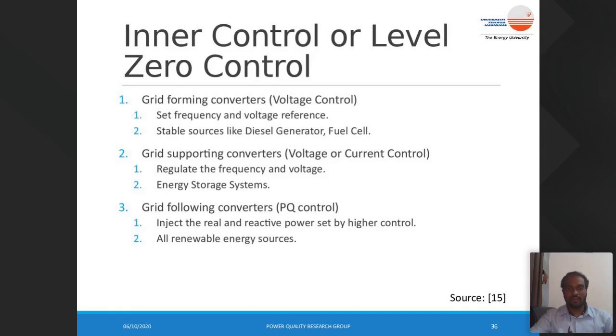And in case of an isolated microgrid, there would be at least one grid forming converter to set the frequency and voltage reference. And these converters are usually fed by stable sources like diesel generators or fuel cells or any other energy storage system which can deliver power for a longer duration. Whereas the grid supporting converters play the role of regulating the frequency and voltage. And predominantly these are also stable sources like energy storage systems and diesel generators or even fuel cells for that matter. And finally, we have grid following converters.